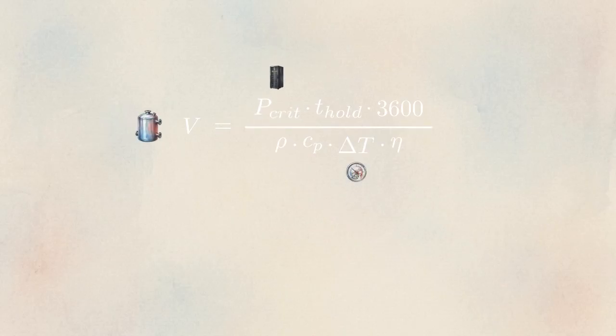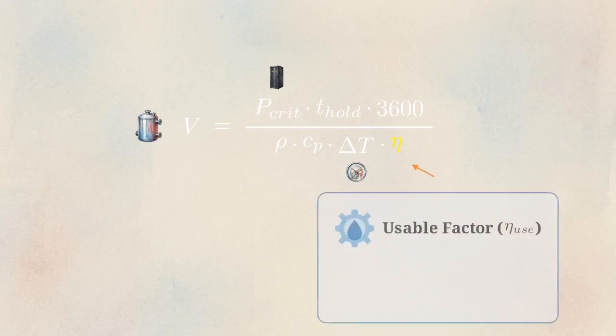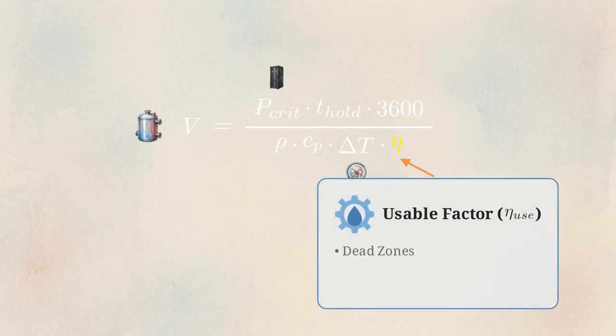To prevent a shortfall, the required volume is calculated using this formula, which factors in the critical power load and required hold time. Notice the variable at the end, the usable factor, which mathematically corrects for that lost volume.